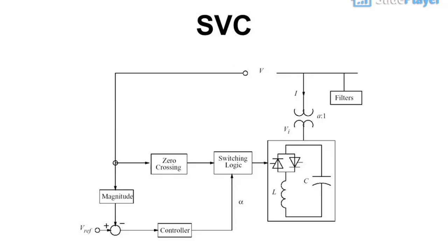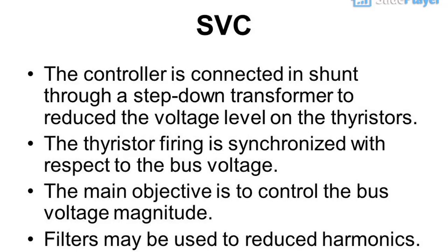SVC: the controller is connected in shunt through a step-down transformer to reduce the voltage level on the thyristors. The thyristor firing is synchronized with respect to the bus voltage. The main objective is to control the bus voltage magnitude. Filters may be used to reduce harmonics.